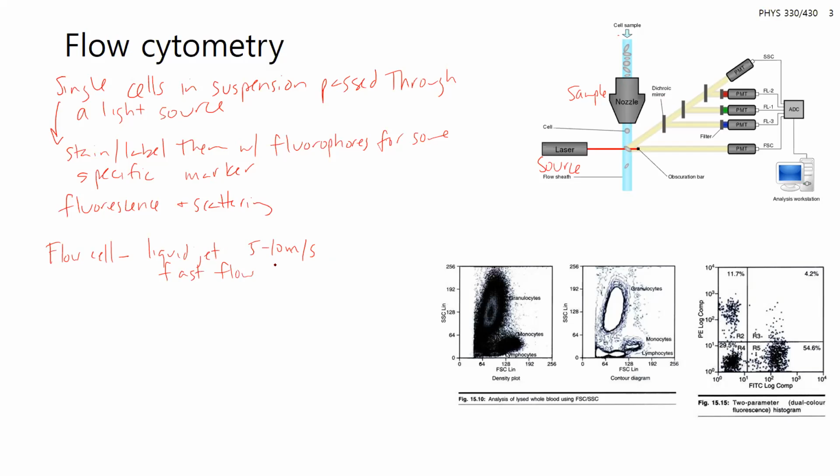That flow, and sometimes it's a microfluidic technique, will isolate individual cells in that stream. And so that's what's passing through here. The laser light will then hit that cell. The light will interact with the cell, and for the detection, all of this right here is a fluorimeter or spectrometer type setup.